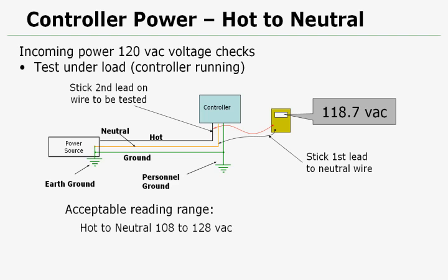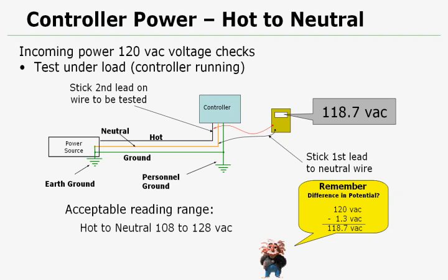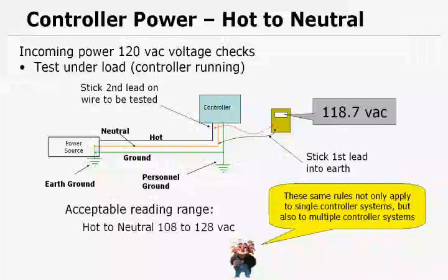Now using the examples we've got so far, notice that we had 120 volts, then from neutral to ground had 1.3 volts. The difference in potential is 118.7, so it all makes sense. We did three readings. You can see the three readings and how they all intertwine. Remember, these same rules not only apply to single control systems, but they also apply to multiple controller systems.